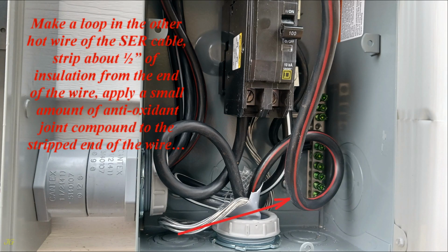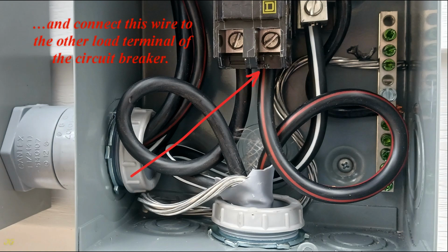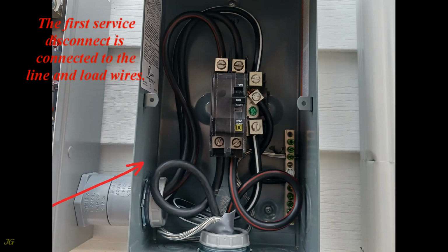Make a loop in the other hot wire of the SER cable. Strip about 1/2 inch of insulation from the end of the wire. Apply a small amount of antioxidant joint compound to the stripped end of the wire. And connect this wire to the other load terminal of the circuit breaker. The first service disconnect is connected to the line and load wires.